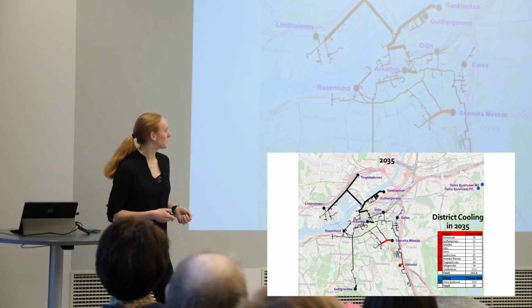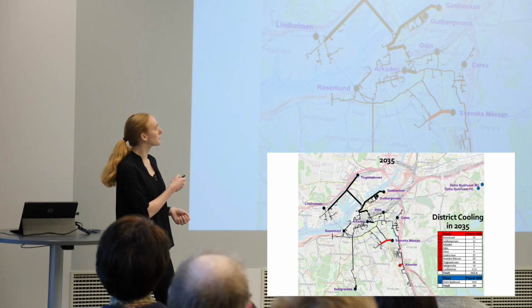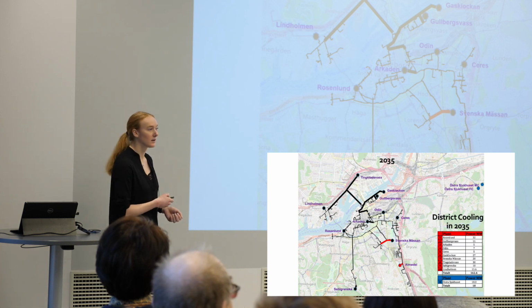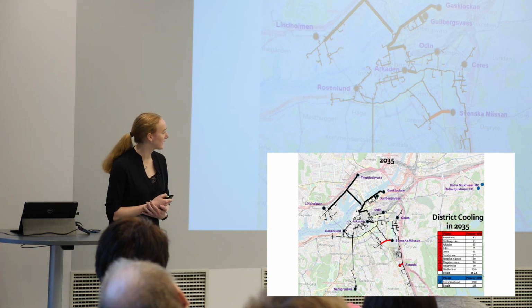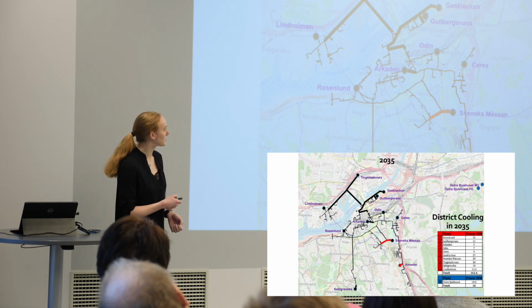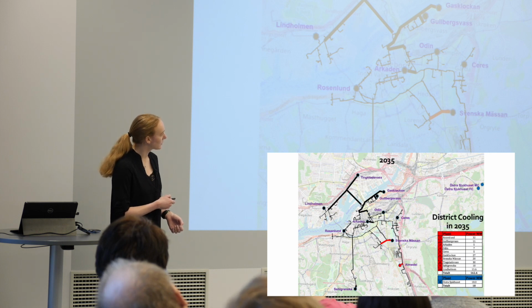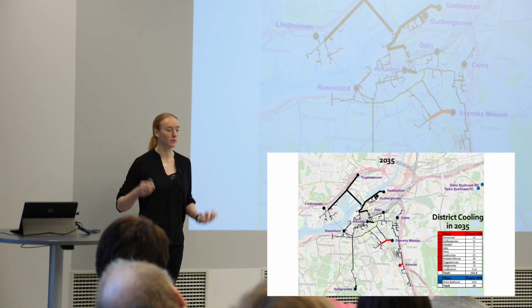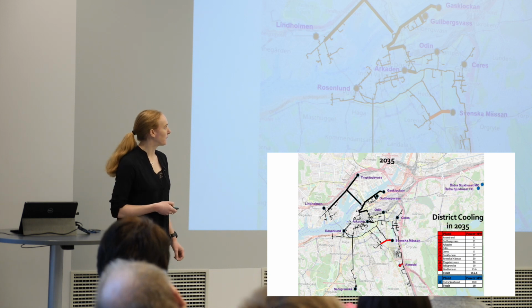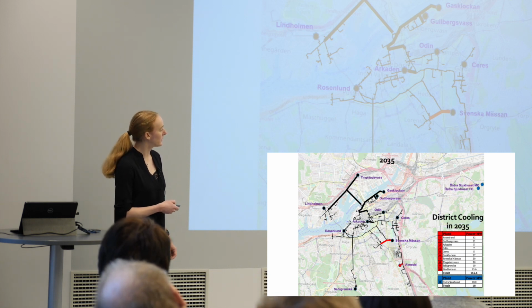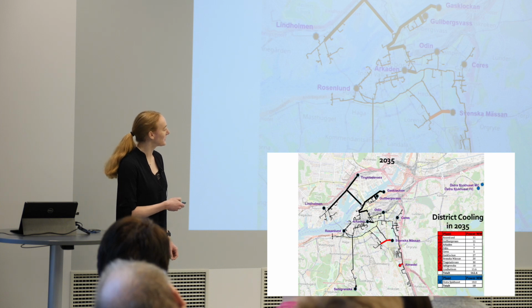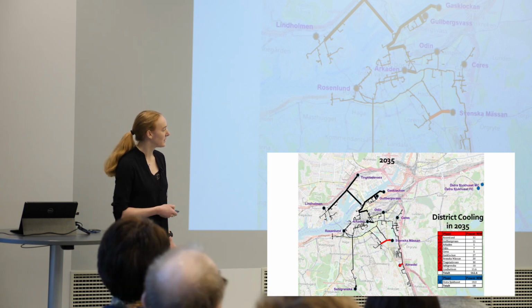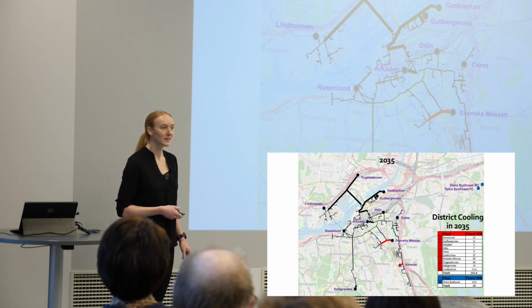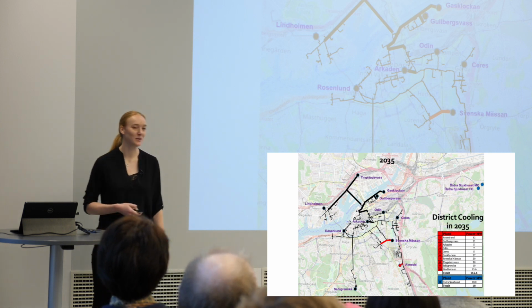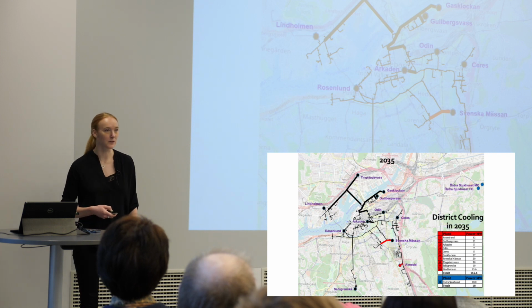And then the plan is also to add more capacity, and up here there's supposed to be a tank, a cold water tank, or thermal energy storage, and some more major pipelines will be built in different parts of the city, and more production will be added in each corner of the network to provide for the increased cooling demand. And so when this has been done, the total installed capacity will be around 163 megawatts. That's more than double the current installed capacity.